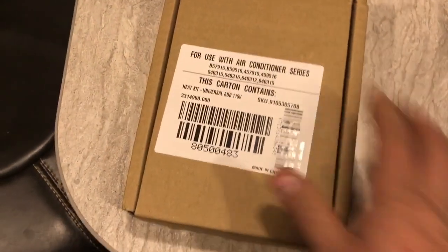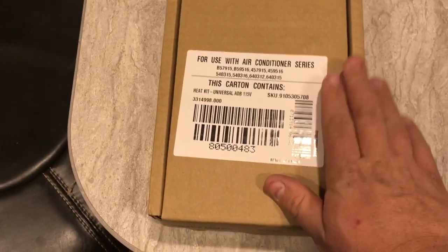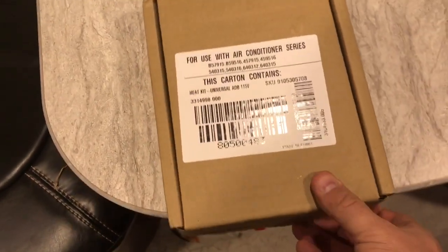Hi, I'm Ed and today I'm going to do the install of the optional heat option for the Dometic roof-mounted non-ducted air conditioner unit. This is the kit for the non-ducted add-on for the Dometic roof-mounted air conditioner unit on top of our trailer.